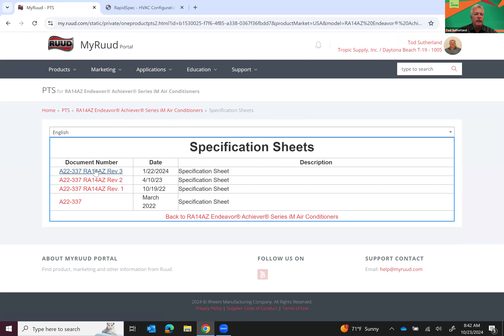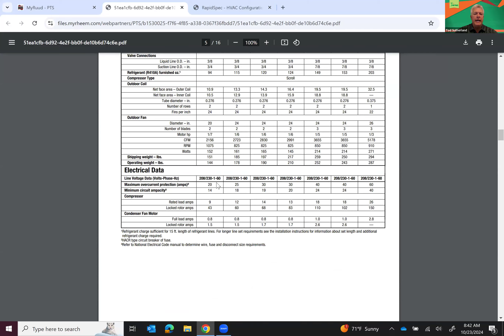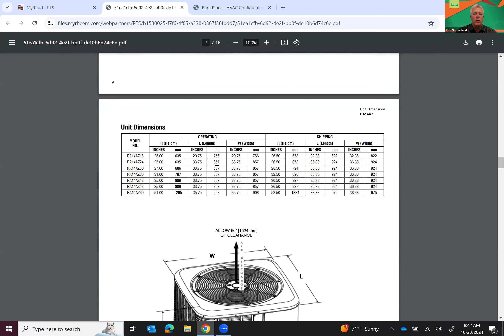bear with me. And we're going to go to condensing units, and we're now going to look at that RA14AZ, and we're going to look at the spec sheet. We're going to select the latest spec sheet, and we are going to scroll down until we get to the AHRI listed data for this equipment, because this can get you in trouble. So you need to pay attention to this.